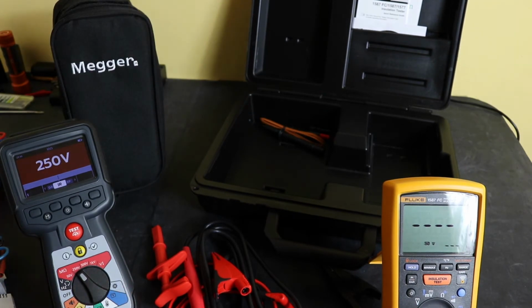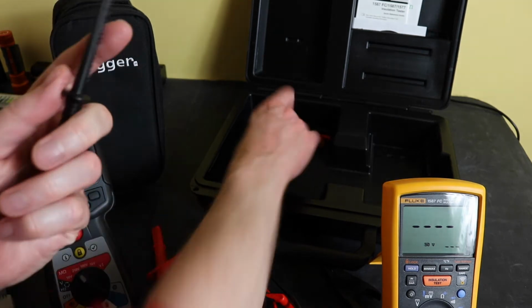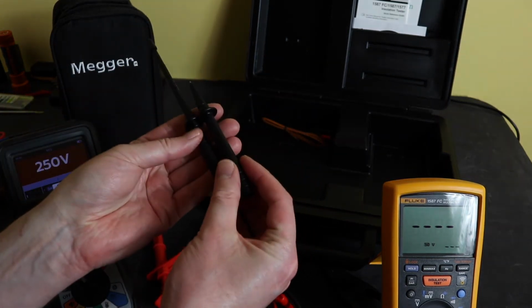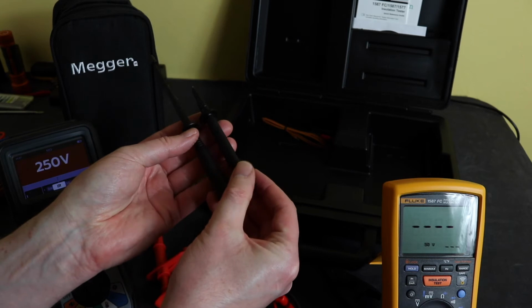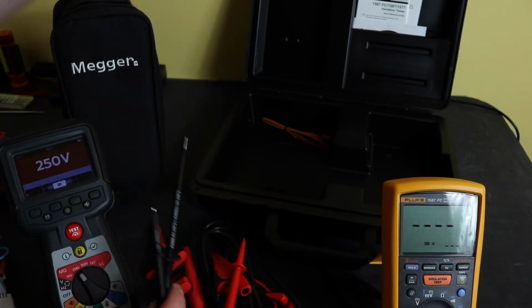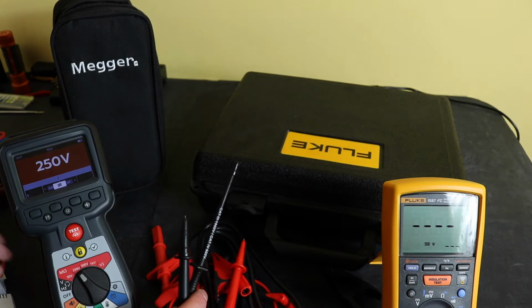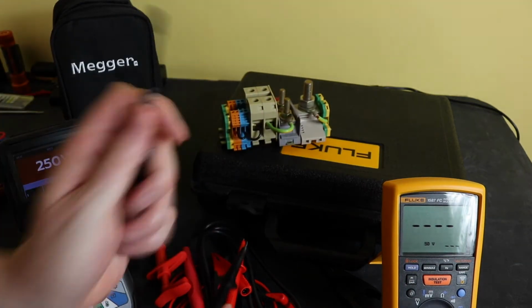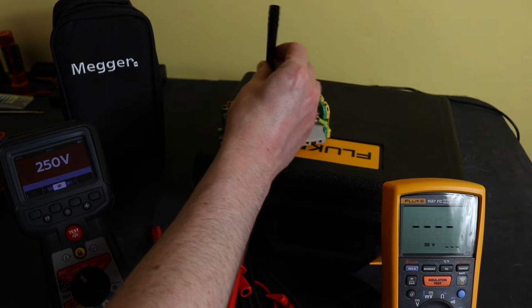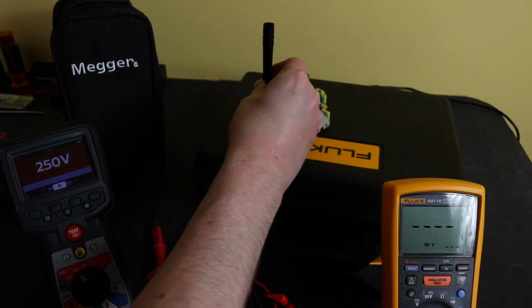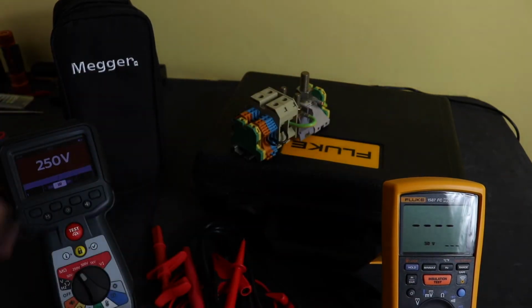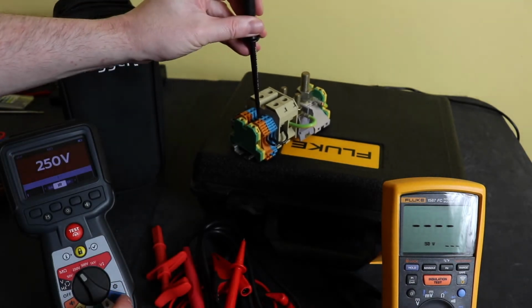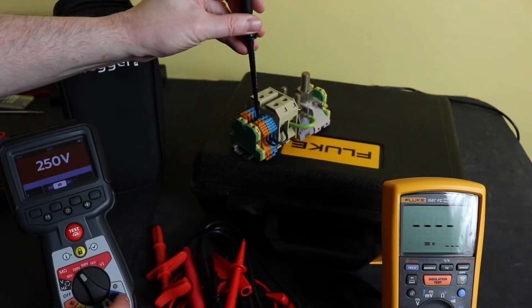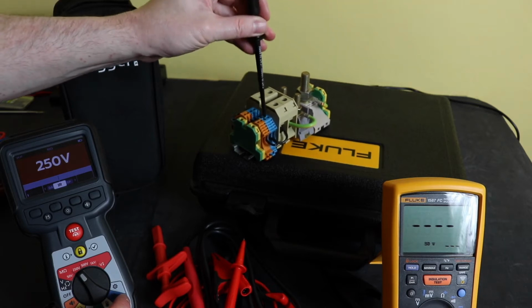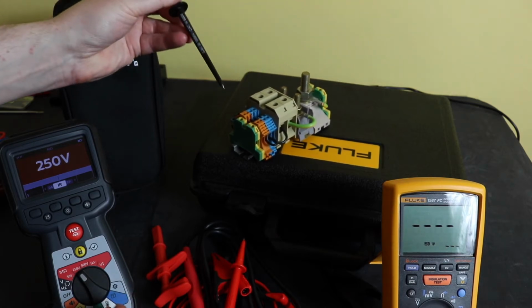Probe wise, it's the opposite way around. In actual fact, with the probes, you get these long reach probes with the Megger here. You get these kind of standard probes with the Fluke, and put these into the terminals. You can see here that it fits okay, makes a reading. But when you get to the smaller terminals, you can't get in there with that. Whereas with the probe from the Megger, you get in quite easy. You don't get into this smaller 2.5, but the 4mm there, you're getting in dead easy with this.